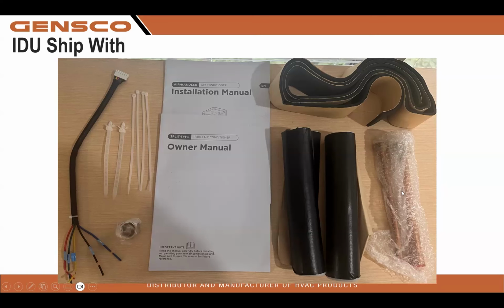And right here is our flare connections. We can flare directly to the equipment, or we can attach these flares with these stubs, 3/8, 3/4 stubs, and braze right onto the end of these. And they are flexible. You can basically bend them right into a 90 with your bare hands, and they won't kink.